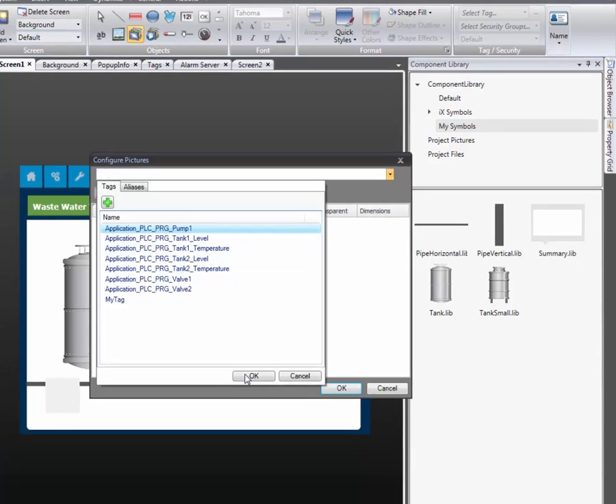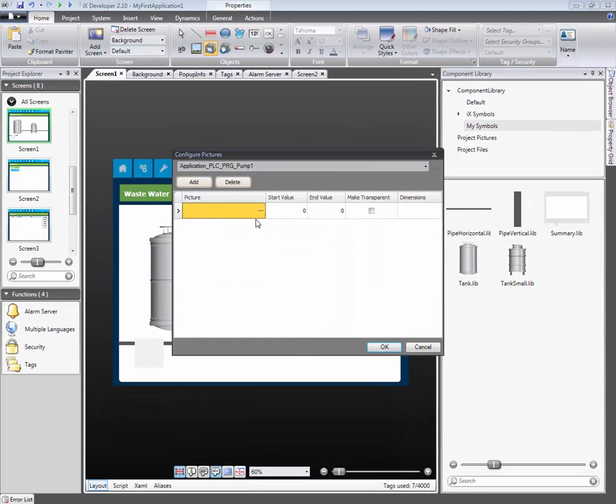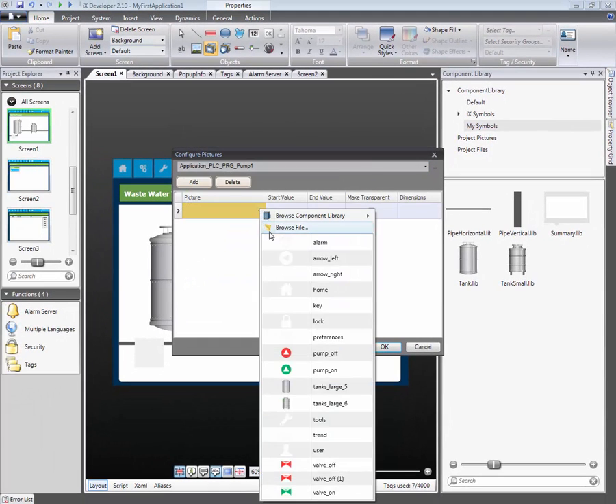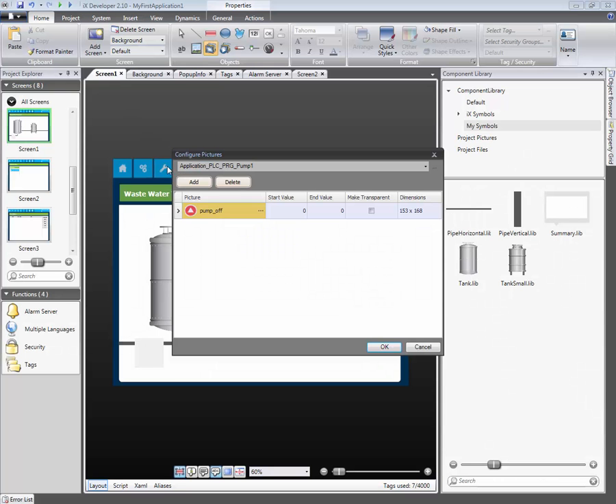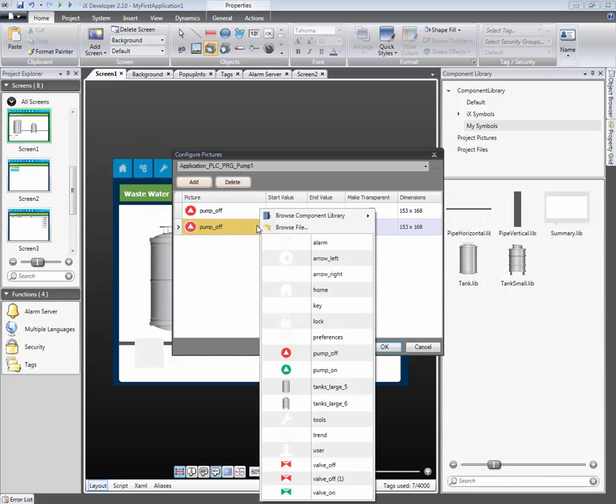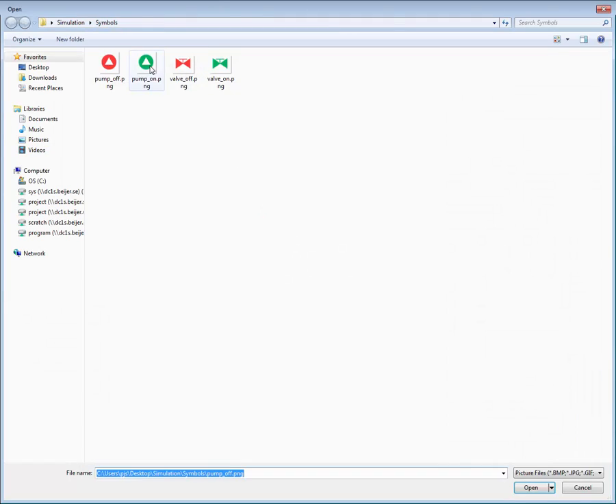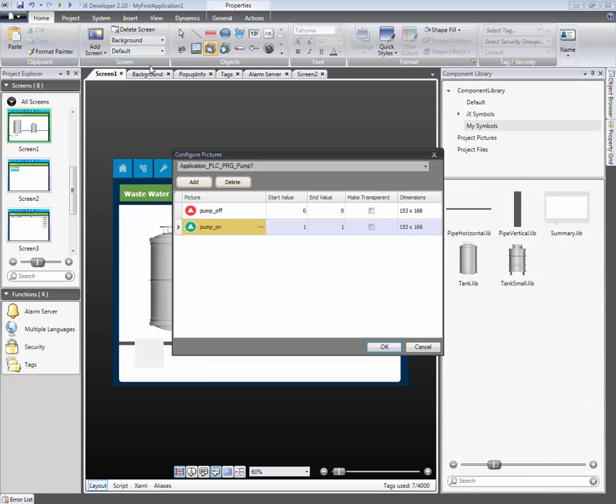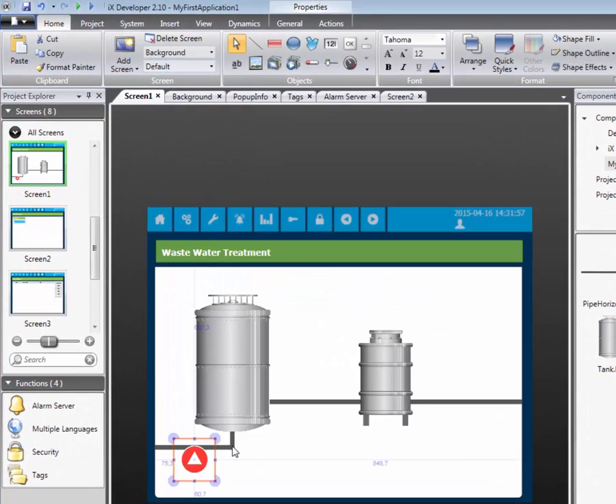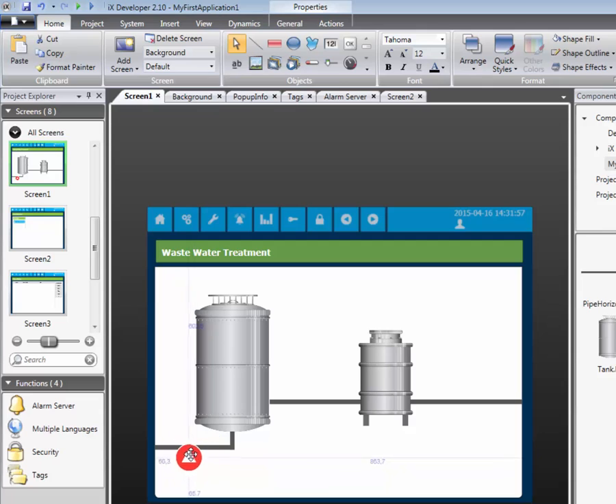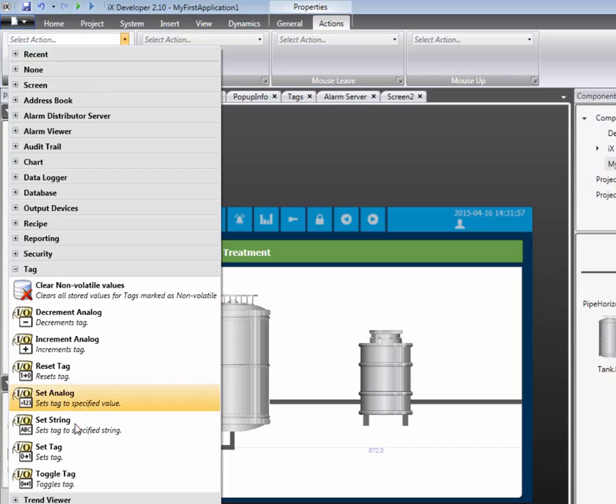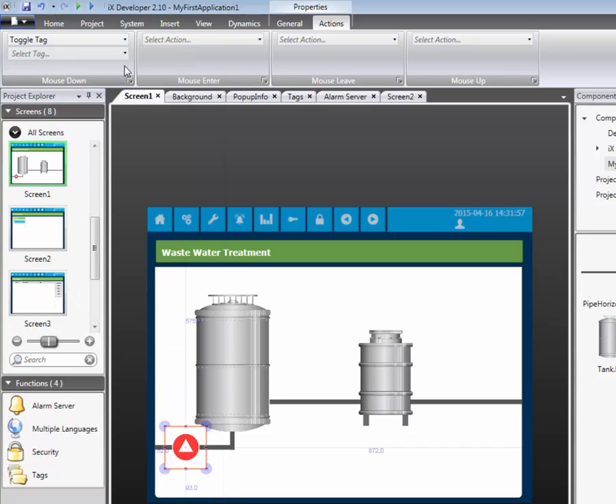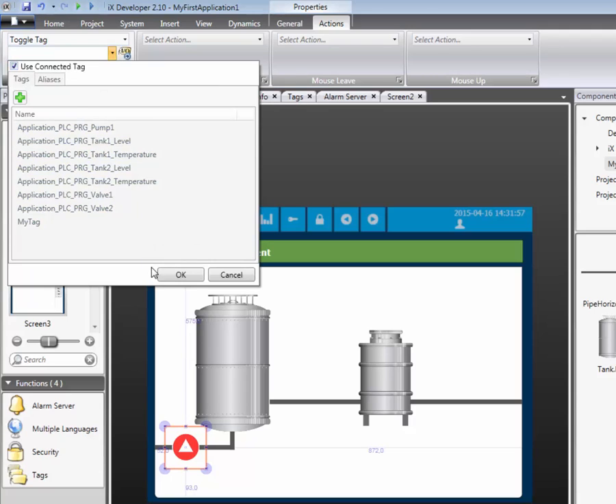Now we need to select which pictures that should be displayed. The first picture will be displayed when the tag value equals zero. The second picture will be displayed when the tag value equals one. By adding a toggle tag action, we will allow the operator to start and stop the pump by clicking on the pump icon.